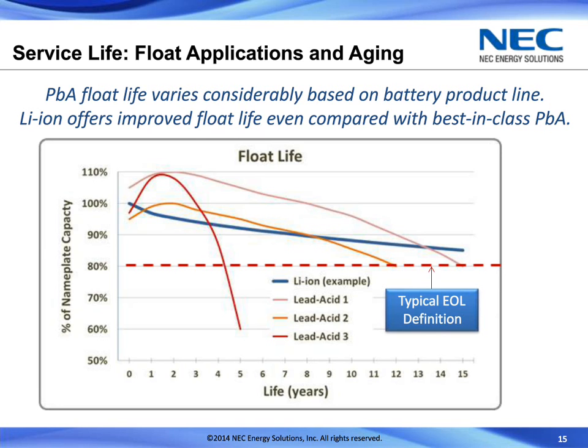There are certainly lead-acid batteries that are optimized for cycle life that can be in a float application and lasting up to 15 years, some up to 12 years as illustrated here. On the other hand, the lithium-ion offers some improvements in float life compared to even the best-in-class backup-type lead-acid battery, in having a float life that would exceed past 15 years. There are certainly other things that might cause that battery to wear out before the actual float service life would be. This allows the lithium-ion battery to provide more capability for a longer period than most lead acids, even those that are optimized for the float life.